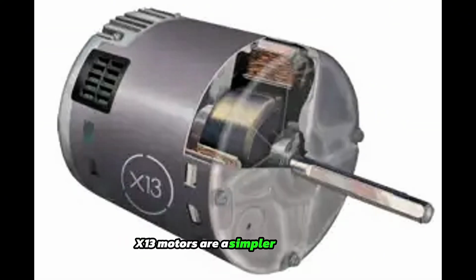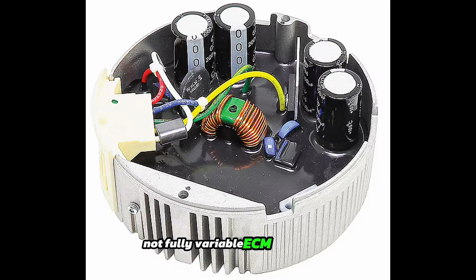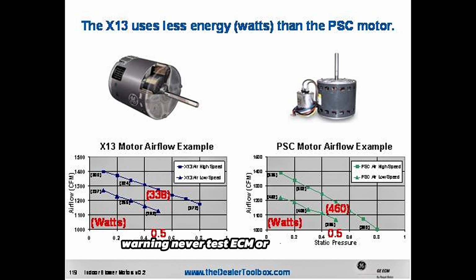X13 motors are a simpler version. They still have multiple speeds, but they're pre-programmed, not fully variable. ECM motors, especially ECM 2.3 and 3.0, are fully programmable and much more advanced. Warning: never test ECM or X13 motors like a PSC motor. They use DC signal logic, and applying 240 volts directly to the wrong terminals will destroy the motor.